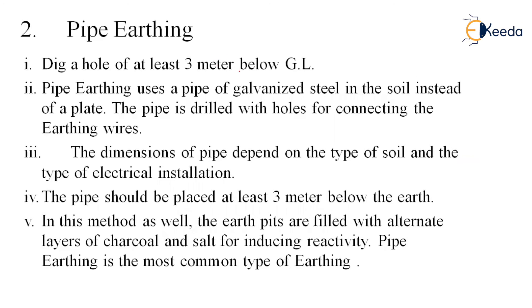Now, pipe earthing. The same procedure applies — dig at least 3 meters below ground level. Pipe earthing uses a pipe of galvanized steel inserted vertically into the soil instead of a plate. The pipe is drilled with holes for connecting the earthing wire. The dimensions of the pipe depend on the type of soil and the type of electrical installation, which can be consulted from the IS code. The pipe should be placed at least 3 meters below the earth. The earth pit is filled with alternate layers of charcoal and salt. Pipe earthing is the most common type of earthing.